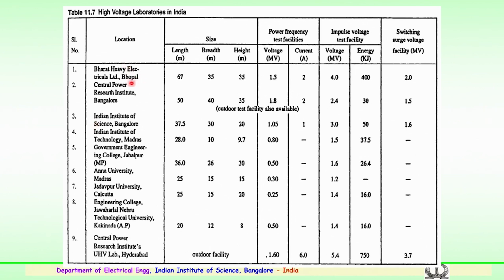The laboratories are available at Bharat Heavy Electricals Limited. They have a high voltage lab of size 67 meters by 35 by 35 meters in height, and they have power frequency equipment of 1.5 million volts with a current rating of 2 amps, an impulse test facility of 4 million volts with an energy of 400 kilojoules, and a switching surge facility of 2 million volts. Then the Central Power Research Institute has a number of laboratories across the country. They have them at Bhopal, Hyderabad, Bangalore, and several other places. One of the labs at Bangalore is given as 50 meters by 40 by 35, the high voltage lab, having a power frequency of around 2 million volts and a current rating of 2 amps, impulse of 2.4 million volts and 30 kilojoules energy, and 1.5. These statistics could be of earlier values.